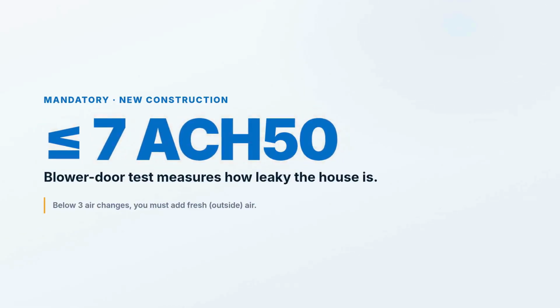Now, in Florida, for new construction, a blower door test to see how leaky your house is is mandatory. You can't get away from it. And in Florida, that's 7 air changes or less. And anything below 3 air changes, you have to actually bring in outside air. A duct leakage test is not mandatory in new construction if you're not using the prescriptive method. In the prescriptive method, you have to have a duct leakage test, and you actually have to meet a certain criteria.